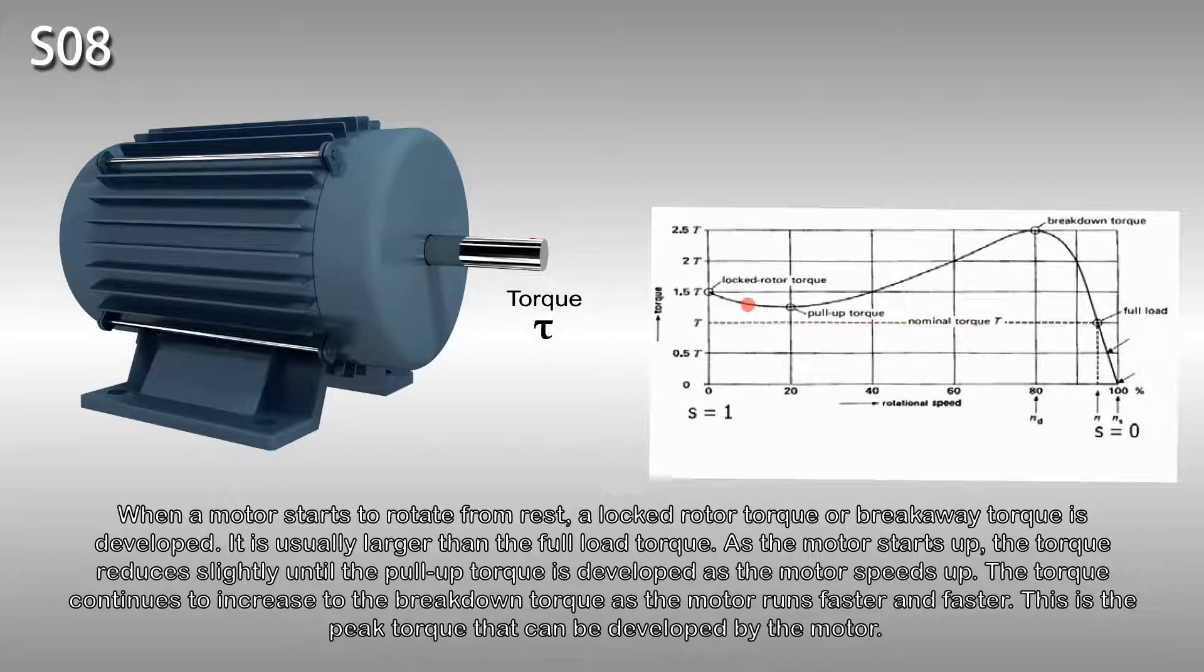As the motor starts up, the torque reduces slightly until the pull-up torque is developed as the motor speeds up. The torque continues to increase to the breakdown torque as the motor runs faster and faster. This is the peak torque that can be developed by the motor.